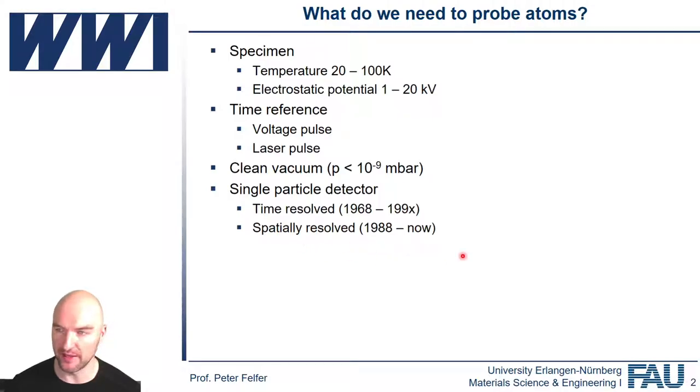And that's why we're looking at delay line detectors. They're not the only spatially resolved detectors. In the early days of tomographic atom probe, people used to use wedge and strip detectors. They came from astrophysics. They're not particularly capable when it comes to multi-hits. And then the group in France used multi-anode array detectors, and they also have some multi-hit problems. So delay line detectors all the way right now. I'm not saying that's going to be it forever, but that's it for now.